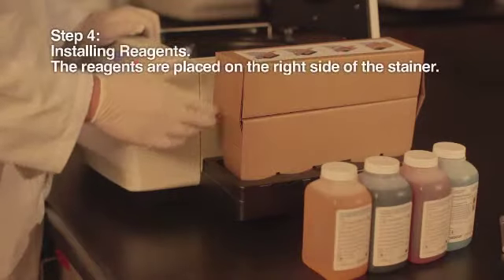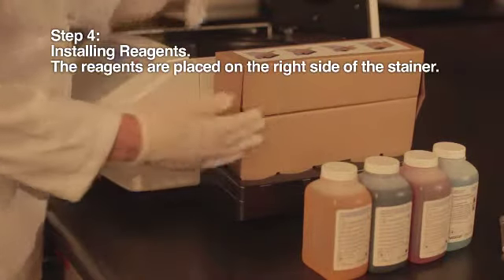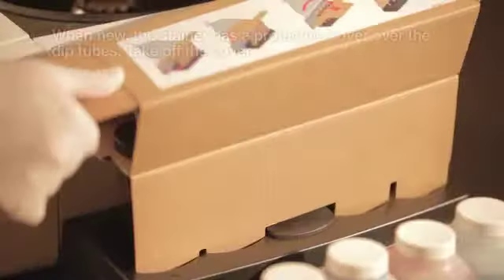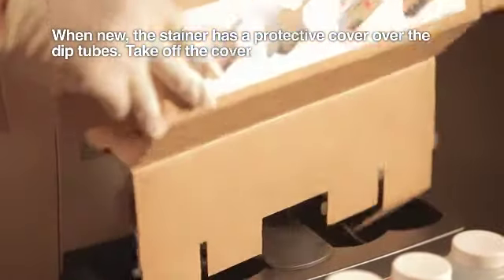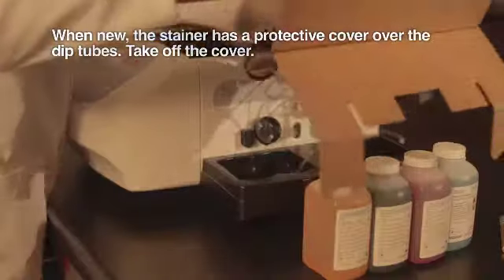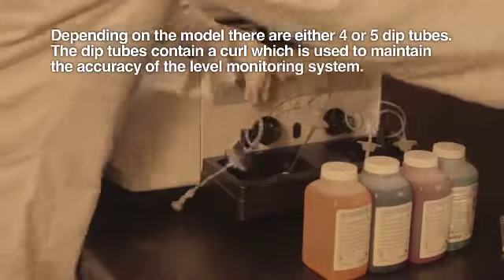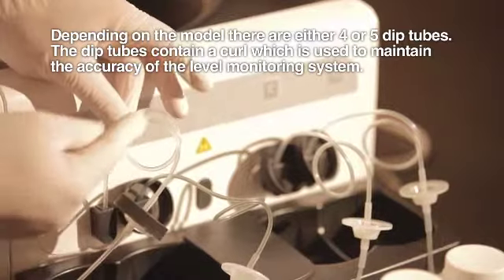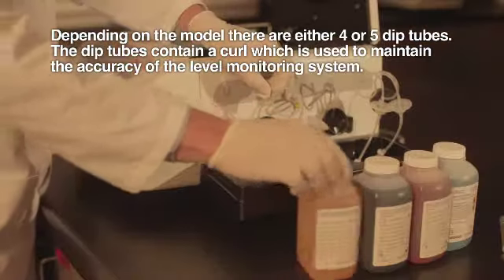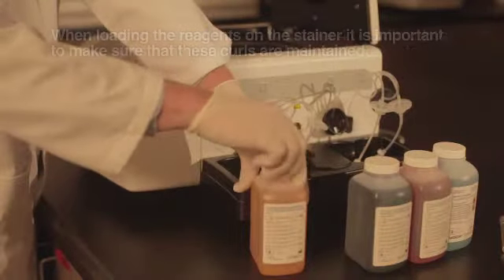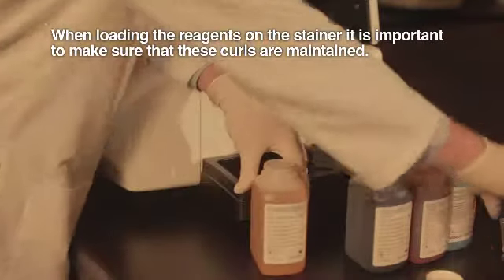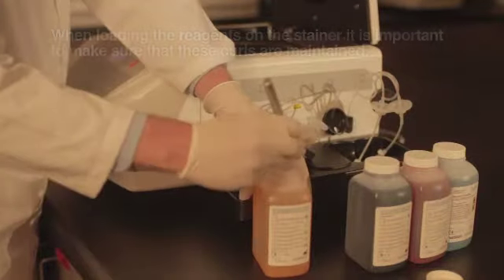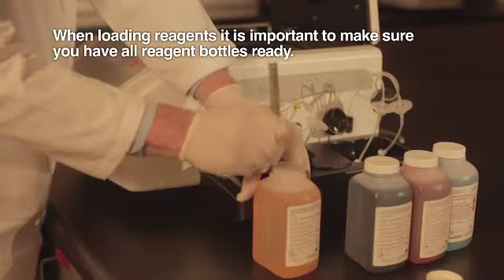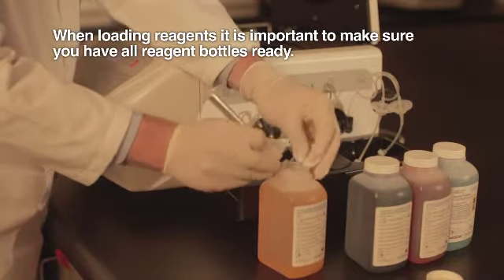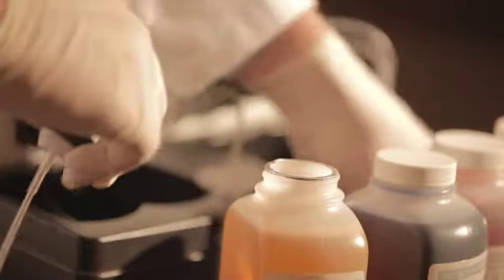Step 4. Installing reagents. The reagents are placed on the right side of the stainer. When new, the stainer has a protective cover over the dip tubes. Take off the cover. Depending on the model, there are either 4 or 5 dip tubes. The dip tubes contain a curl which is used to maintain the accuracy of the level monitoring system. When loading the reagents on the stainer, it is important to make sure that these curls are maintained. When loading reagents, it's important to make sure you have all reagent bottles ready. The specific reagents to load on each line for each model are described later in the video specific to each model.